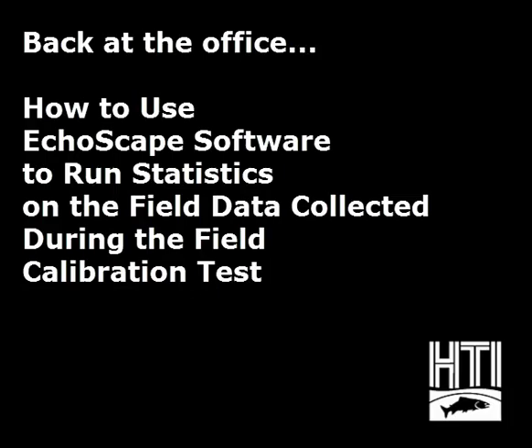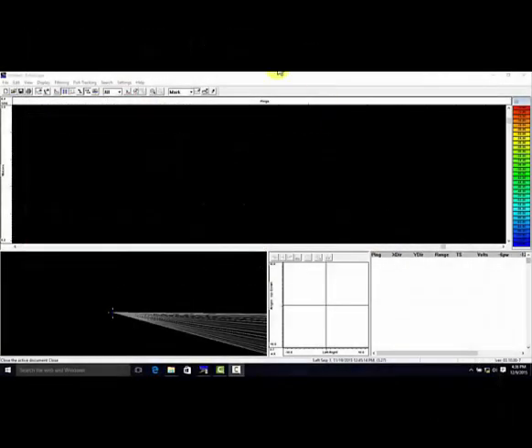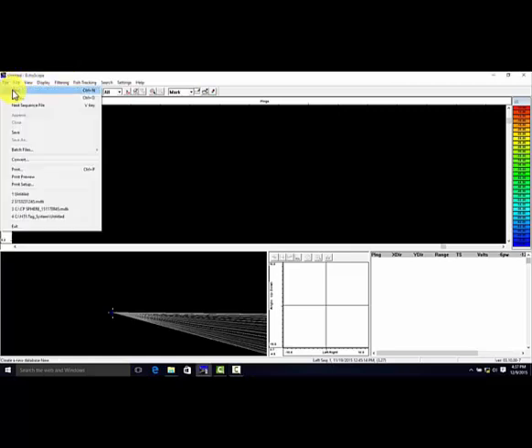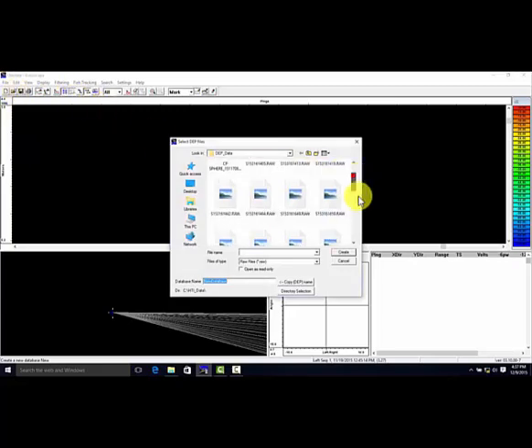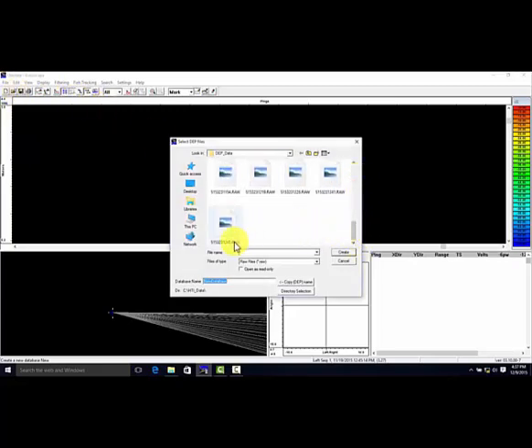Now that we are back in the office, we want to show you how to use our Echoscape software to run statistics on the data that you recorded in the field during your sphere calibration test, and to make sure that you're getting an accurate reading of target strength, that you have enough echoes to validate the statistics, and that your standard deviation is nice and low. To get this started, we already have Echoscape open on our computer, so we will go to File, New, and locate on our hard drive where our raw file is that we created in the field.